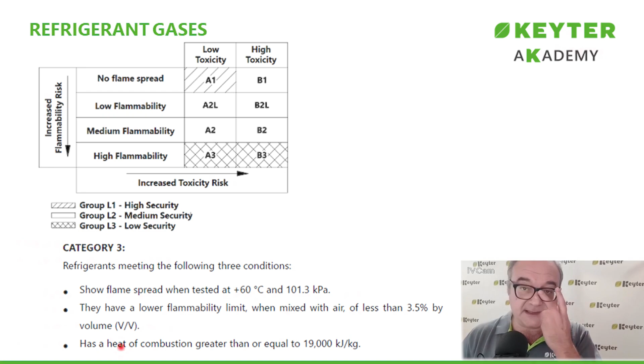We already know that there are three categories for flammability and two for toxicity. Category A would be a refrigerant whose concentration over time has no effect on a worker who is exposed to that refrigerant for 8 hours a day and 40 hours a week. And that threshold concentration value, let's say, is 400 milliliters per cubic meter, which is commonly expressed in parts per million. If you convert the volume, you'll see they are parts per million, ppm.